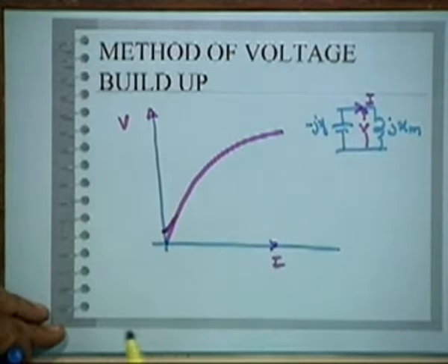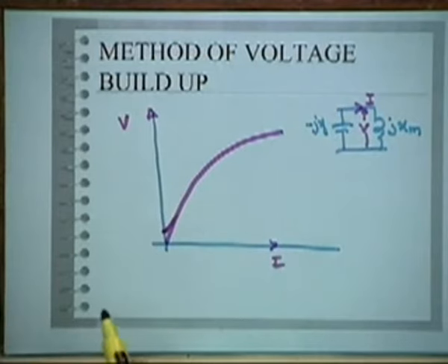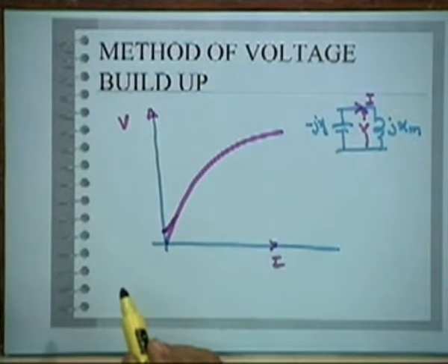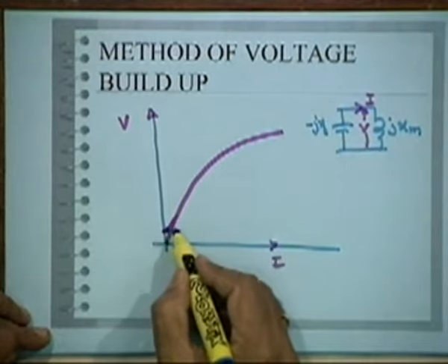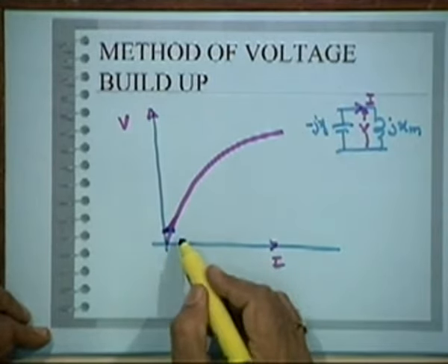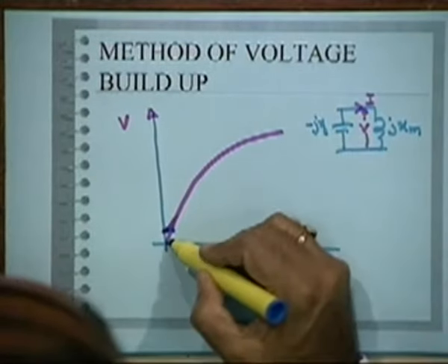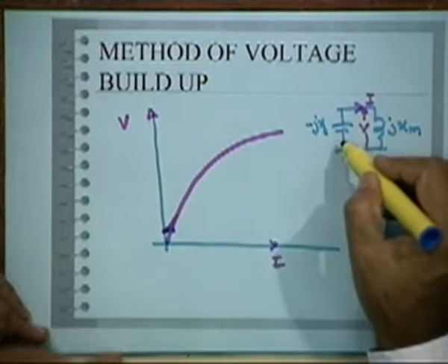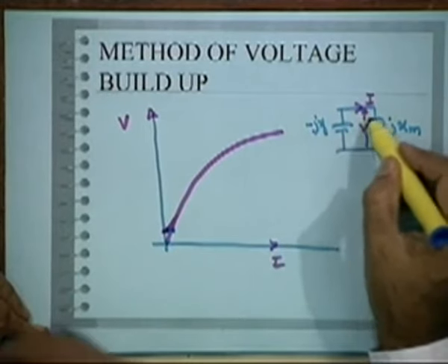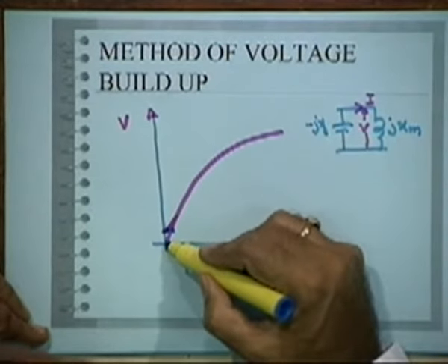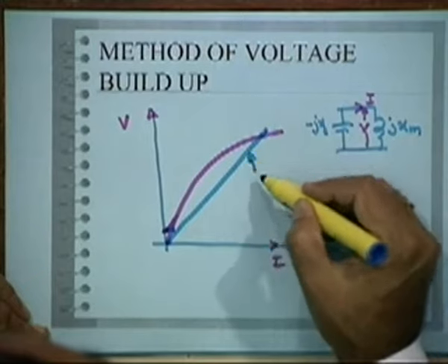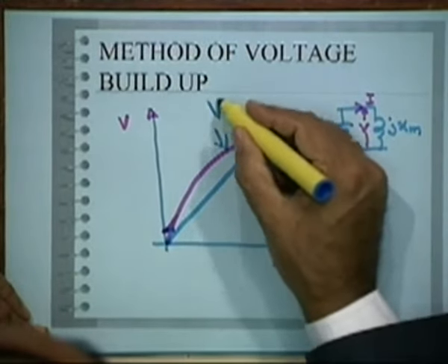Imagine that there is some residue in the rotor, some flux in the rotor. When it is rotating, some voltage will come in the 3-phase windings in the stator, across which you have connected a capacitor. Okay. Now there will be a certain voltage and that will cause a certain current, okay, and across the capacitor there will be a current, and when the current is there there is a voltage across the capacitor. So there is a capacitor line, let us say this is the voltage across the capacitor, this is the voltage across the machine.